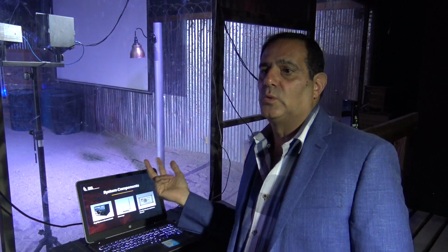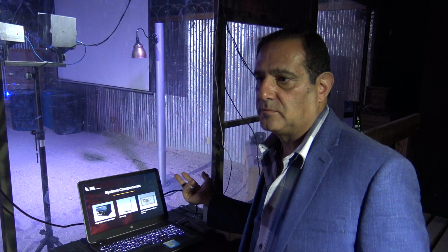In the case that he shoots first, then we disable the pull-downs. Now, if there's a real fire, the smoke and heat sensors are still going to work. The only thing that doesn't work is the pull-down sensor. So this is, for example, what we do with our relays. You can program them for that.